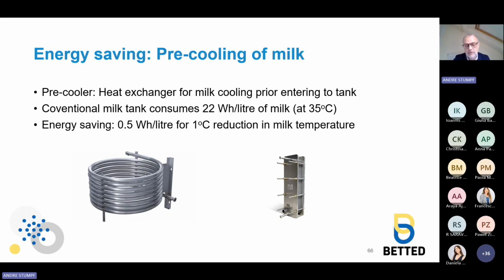So you have two pictures where you can see what we are speaking about. Heat exchangers are designed to maximize the area of the heat transfer surface, which increases friction and pumping head. If a system includes a pre-cooler, it's worthwhile adding a variable speed drive on the milk pump. The energy consumption of the milk tank without pre-cooler is typically 22 watt-hours per liter of milk on average, and it's directly proportional to the temperature of the milk. The temperature of the milk is around 35 degrees C. Consequently, a 1 degree C reduction in milk temperature results in a 0.5 watt-hour per liter reduction in energy consumption by the milk tank. The energy saved by pre-cooling is therefore directly linked to the reduction in the temperature of the milk as it passes through the heat exchanger.